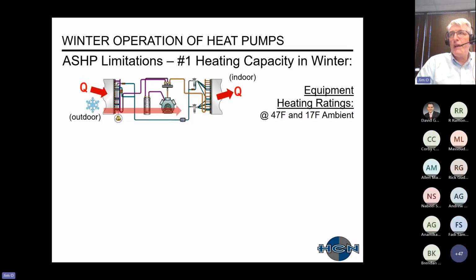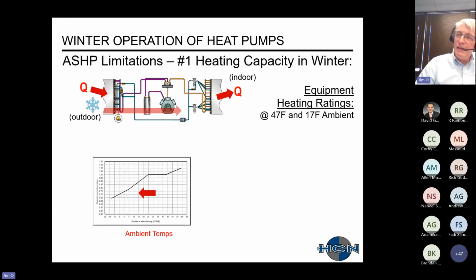Now, the limitations of air source heat pump. The first one I want to bring up is that your heating capacity in the wintertime gets greatly reduced. Equipment ratings from ARI or AHRI for heat pumps are typically done at 47 and 17-degree ambient. This is just a graph, probably a VRF graph actually, that shows just as your ambient temperature drops, your heating output also decreases.